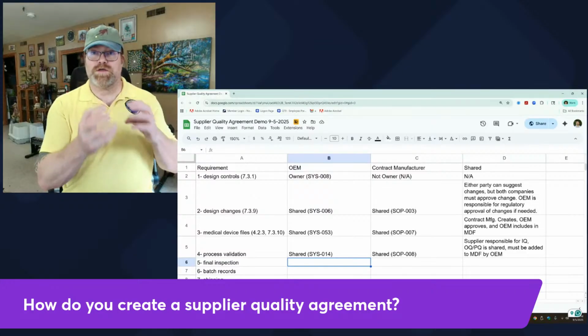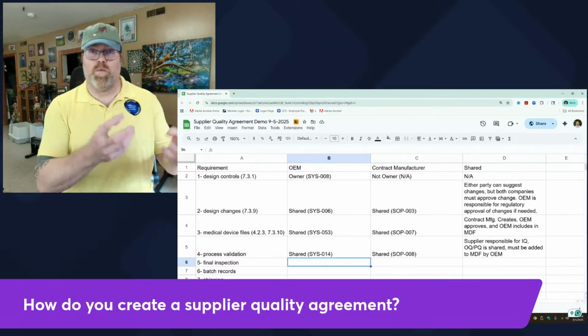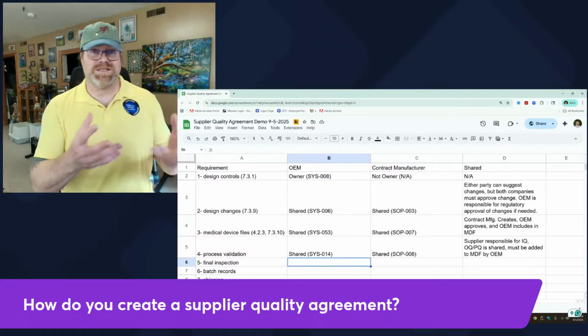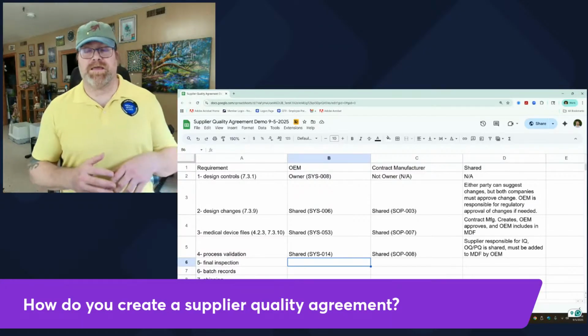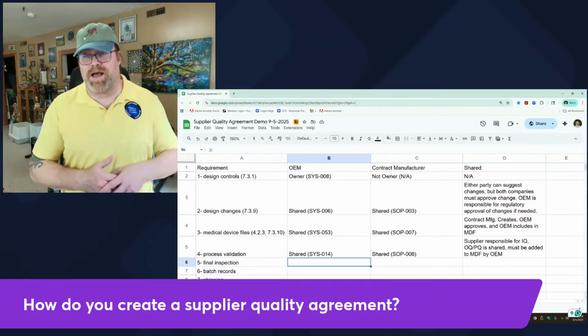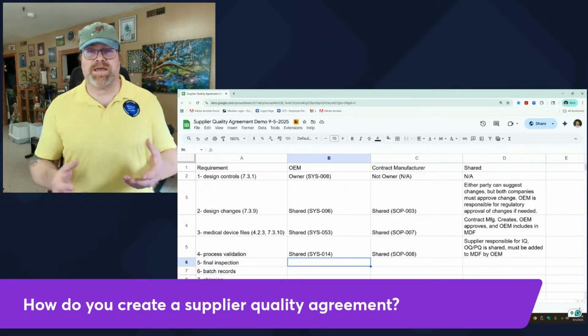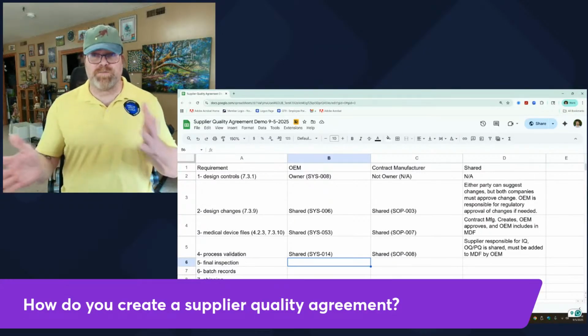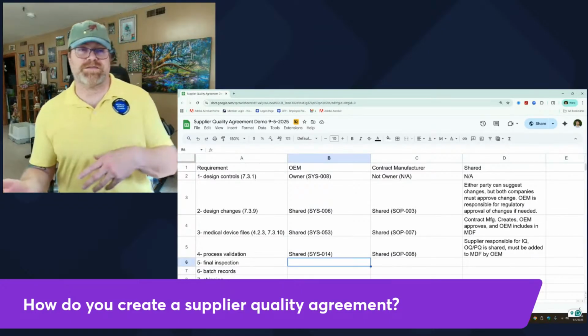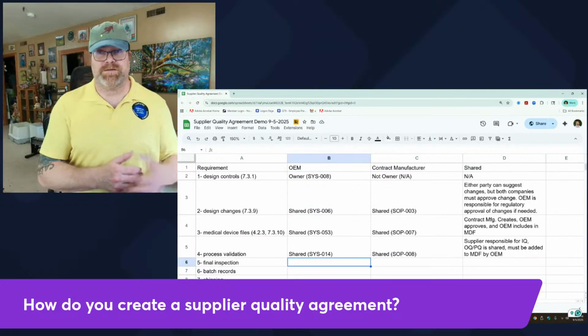The OQ is where you get to play and figure out what the acceptable variation is likely to be. If the process isn't anywhere near where I need it to be, I'm going to have to come up with a new process. But a lot of times we'll be fine with that amount of variation. Now I have to revise the drawing because the process doesn't meet what I thought we could meet.